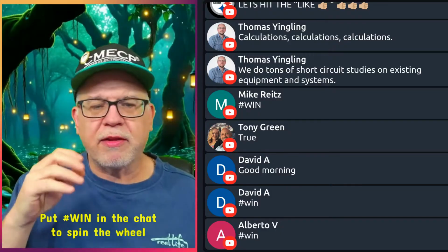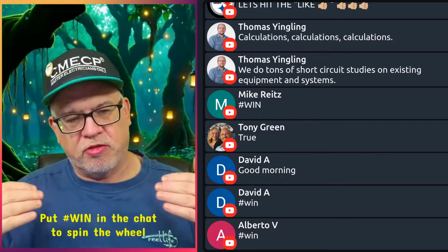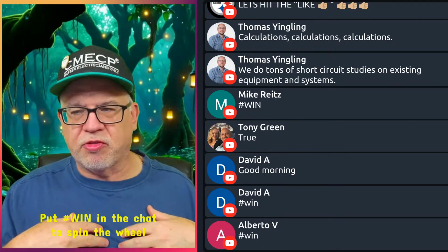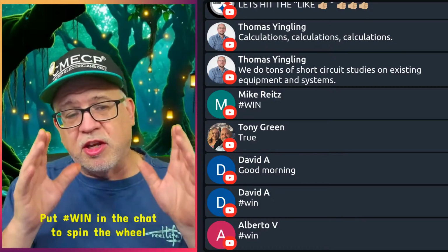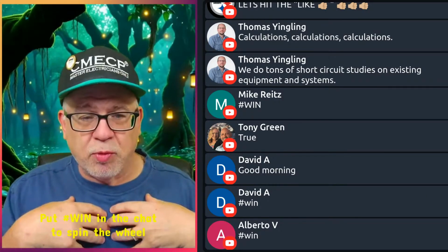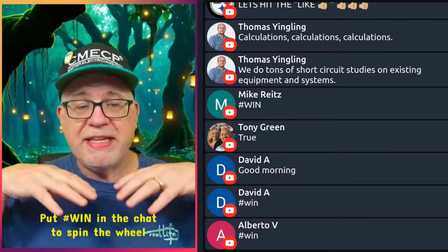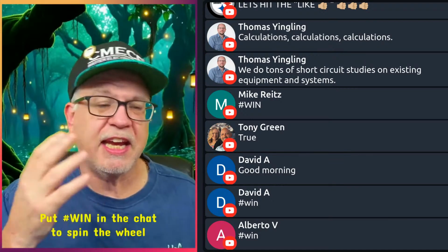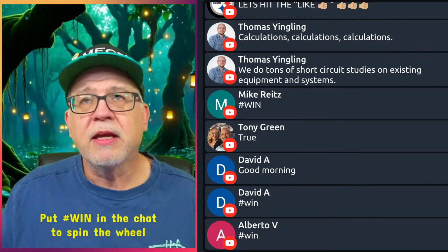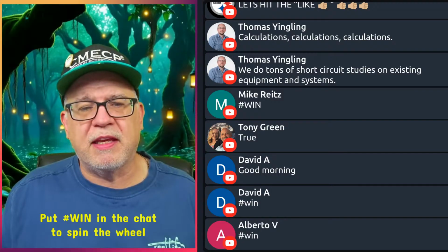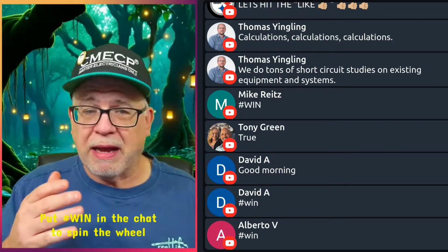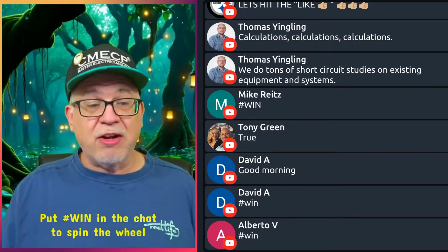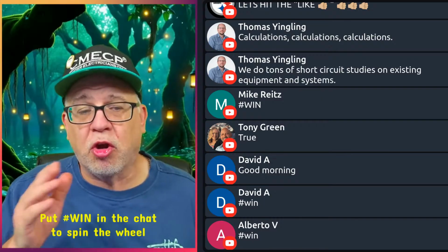At the end of the day, all of this stuff is tested under standard conditions, like wire and cable. So when you call us about things like ambient temperatures or adjustment and correction factors, we tell you to go to the code and we'll help you, but that doesn't change what our wire is rated at or what we tested at. A lot of times people ask me, for example, about non-metallic sheathed cable, NM cable, Romex is trade slang. They ask, what if it's in contact with thermal foam? Is that going to cause a problem with the PVC jacket? And my response, and all of the manufacturers' response, is, I don't know. I'm going to say no because it's been done for years, but you know who you need to ask?